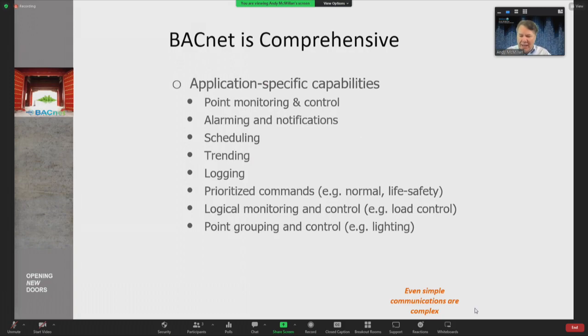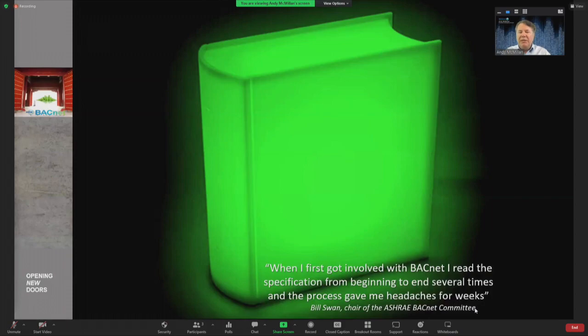The end result is that BACnet, if you actually went to read the spec, is probably 1,500 or 1,600 pages of dense technical text. So I don't recommend that you do that - I don't recommend anybody does that, just reading it from beginning to end. The one person I knew who did that said it gave him headaches for weeks, and I believe it, because it's complicated. Instead, the BACnet standard is really designed to serve as a reference document for developers of BACnet products.